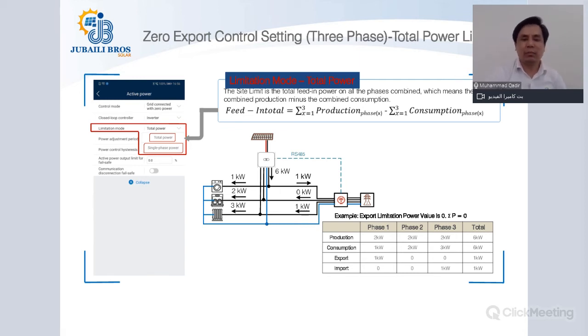What happens when you apply the total power? It will see what is the total sum of the load on all the three phases. As you can see on this screen, the load on all the three phases sums to around 6 kilowatt. Therefore, the total output of this inverter is 6 kilowatt. Though this inverter might be capable of generating more than 6 kilowatt, it has limited its output such that the 6 kilowatt equals the sum of all the three phases.